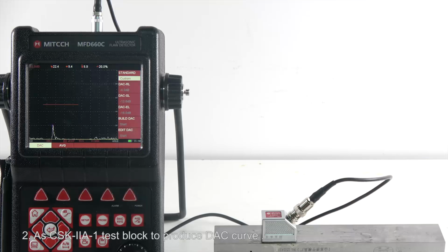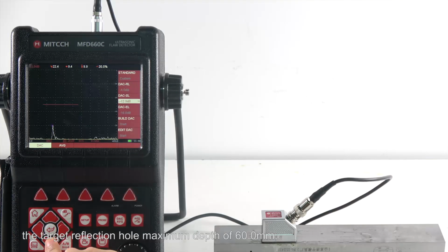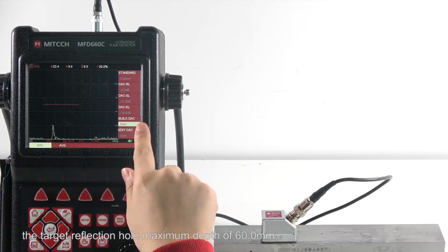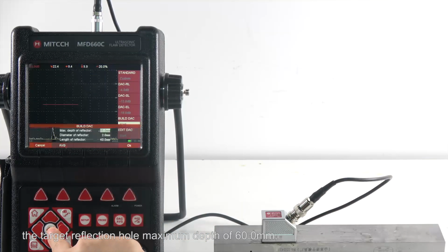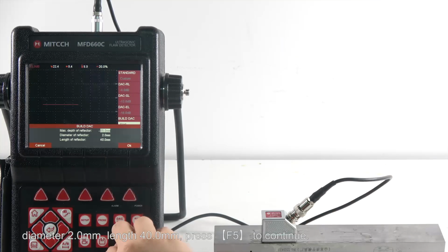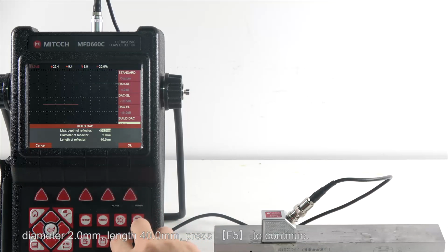Add the CSK2A1 test block to produce the DAC curve. The target reflection hole has a maximum depth of 60.0mm, diameter 2 mm, length 40 mm. Press F5 to continue.